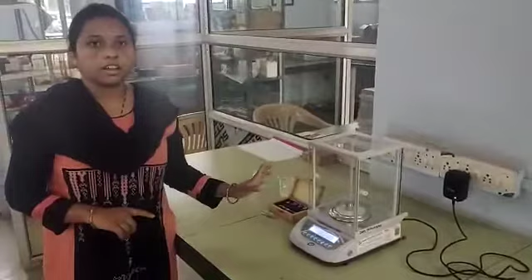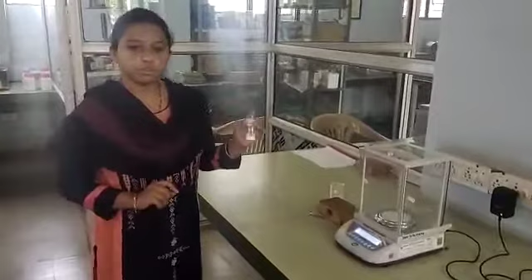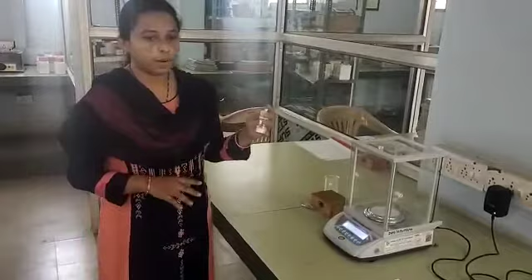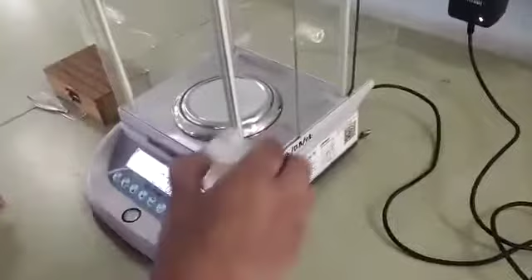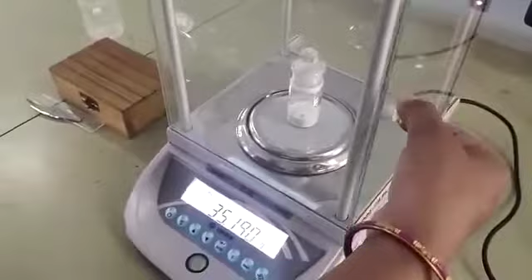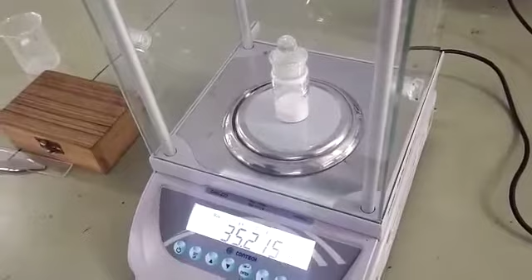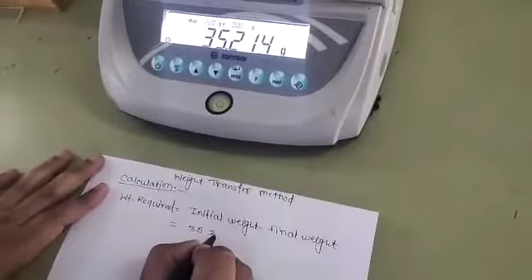This analytical balance stores the weight up to 100 and prints up to 100 weights. We will see the working of the analytical balance. Today I will use the weight transfer method for weighing. For this I have used a weighing bottle. In this we load a bulk amount of powder. First we measure it. First press the tare key to zero the balance. Wait until the count is stable. It is 35.214.